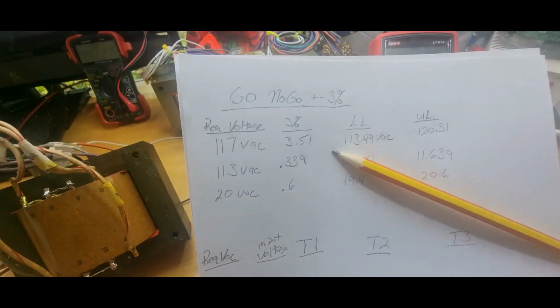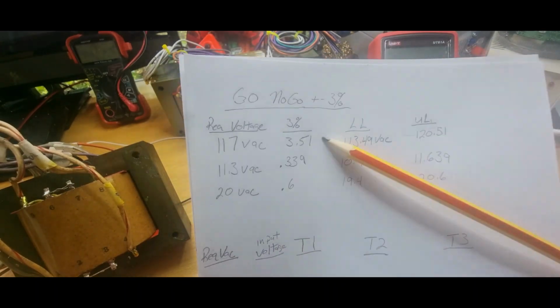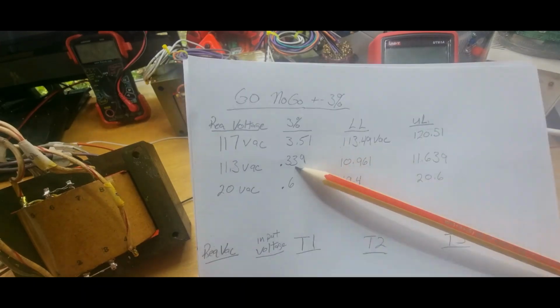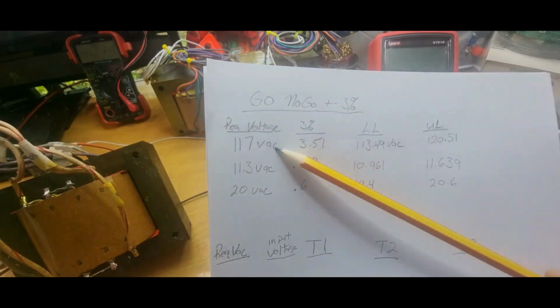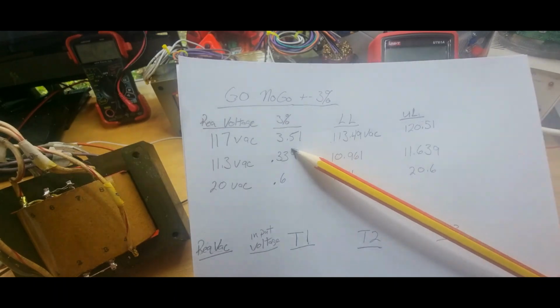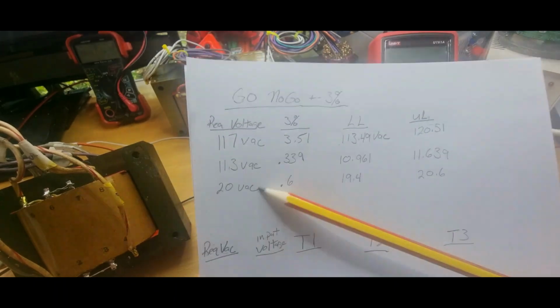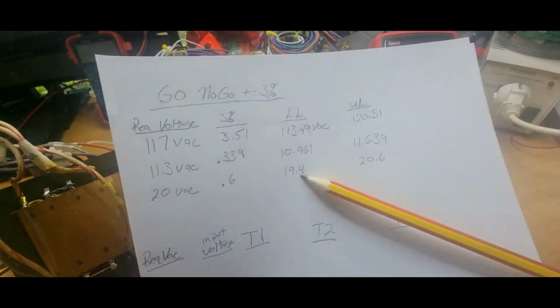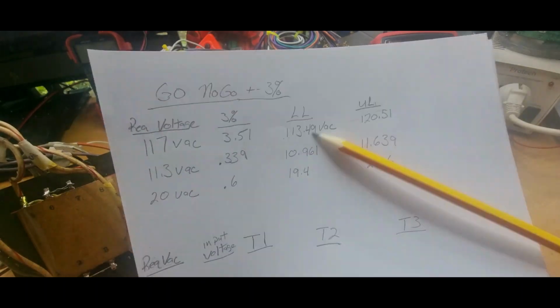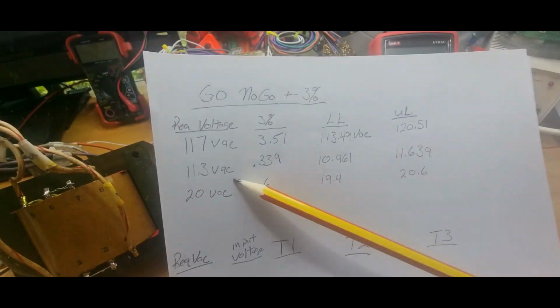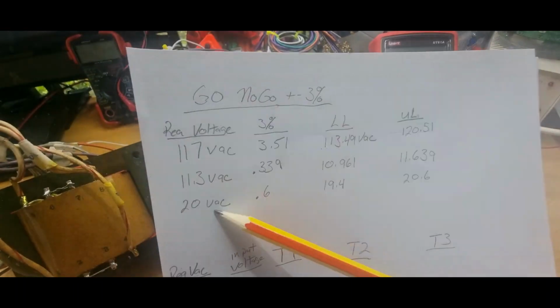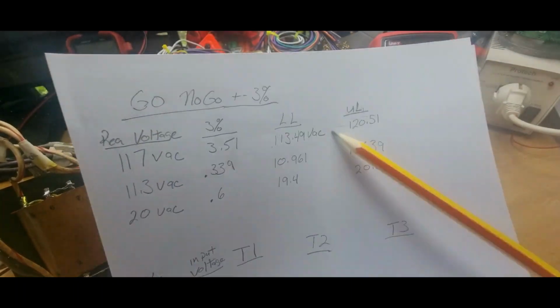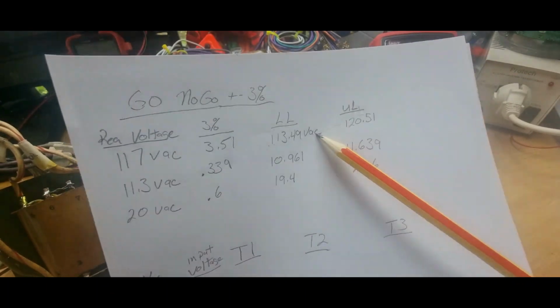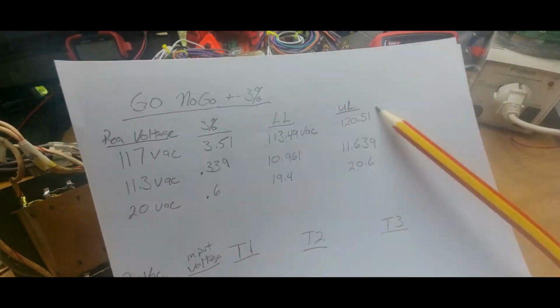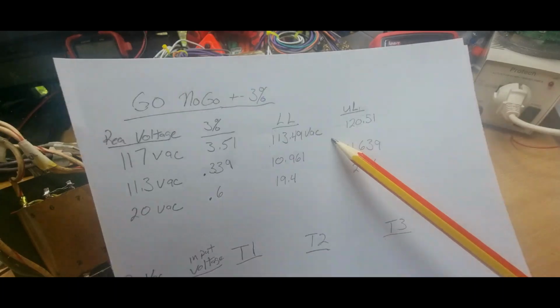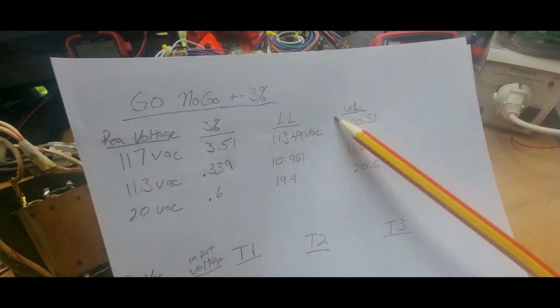The manufacturer gives a percentage limit — your required voltage should be plus or minus 3%. I did the math and created a lower and upper limit for each voltage we're looking for, so hopefully our test readings fall in that range. If you're way off, you'll just have to make a good judgment call.